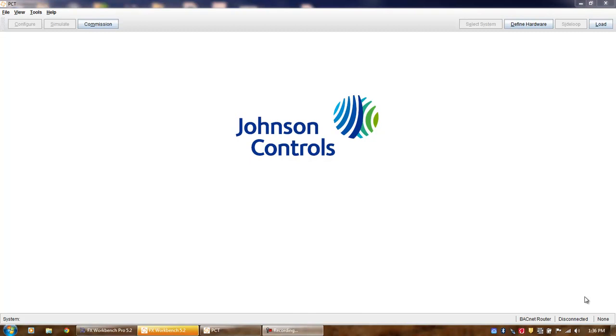This video explains how to use PCT to set up a zoning system based on the FXPC controllers. The system uses a modified mixed-air single-path standard application that is loaded into a PCG for the air handler and a modified standard fan coil application for the zone damper that is loaded into a PCV controller.